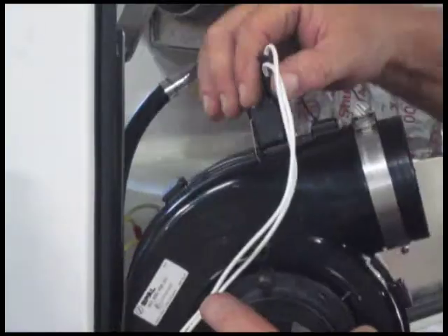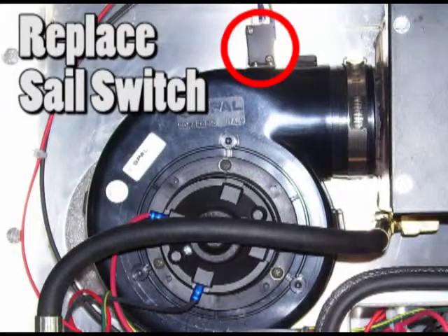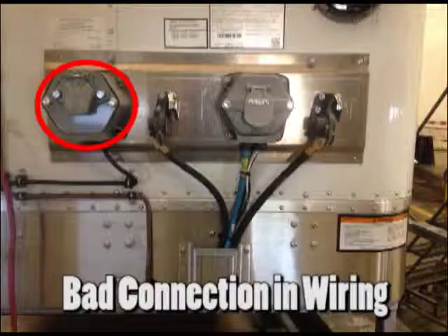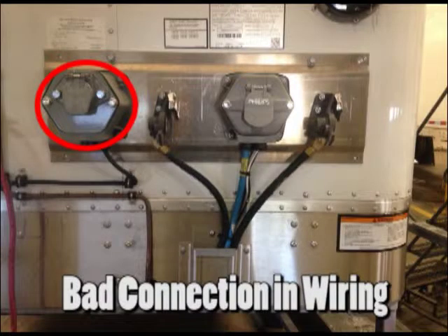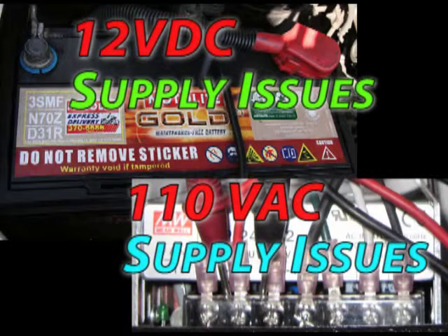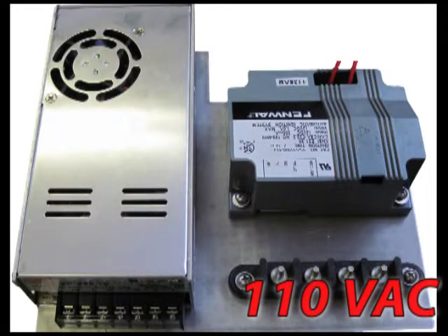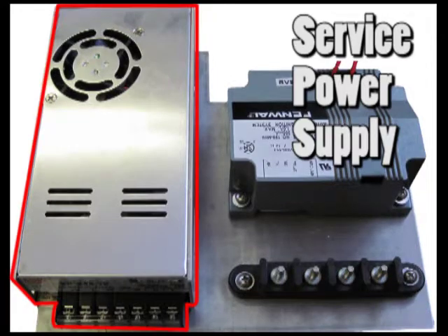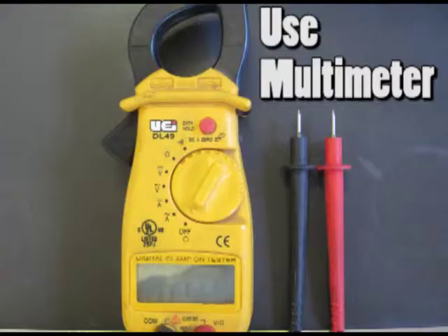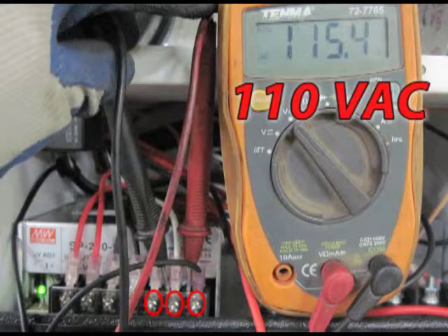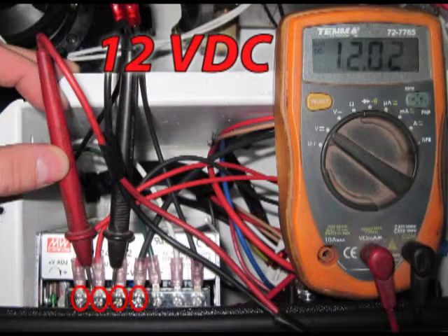Remove the blower and adjust the sail switch if it is stuck. If it isn't stuck, replace the sail switch. If the sail switch wasn't the problem, either there is a bad connection in the wiring supplying power to the heater, or the device supplying power to the heater has significant problems. If the heater is running off of 110 volts AC power, the 110 VAC power supply may need to be serviced. Using a digital multimeter, ensure that the 110 VAC power supply is receiving 110 volts AC and is outputting voltage at 12 volts DC across all 4 terminals.